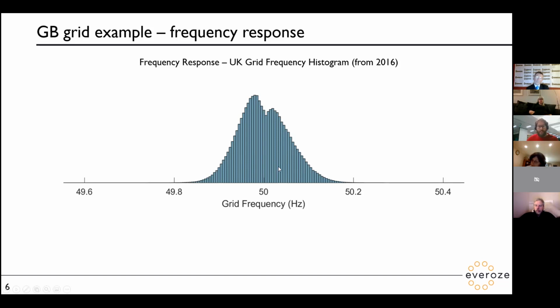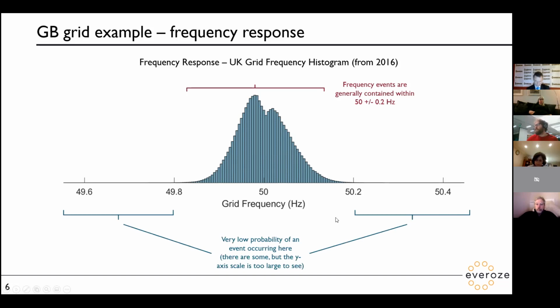Batteries are really good at trying to prop this up, because they're very, very fast. You can just turn a battery on. Unlike a generator or a wind turbine, you don't have to let it speed up. You can turn it on instantaneously, up to full power, 20 megawatts, bang, like that. So batteries are used quite a lot for managing this. Most of the time we're in this sort of range. Very occasionally, you can't even see it on this graph, we're out in these other ranges. And if we're beyond the edges of these, it's really bad news. That just doesn't happen.